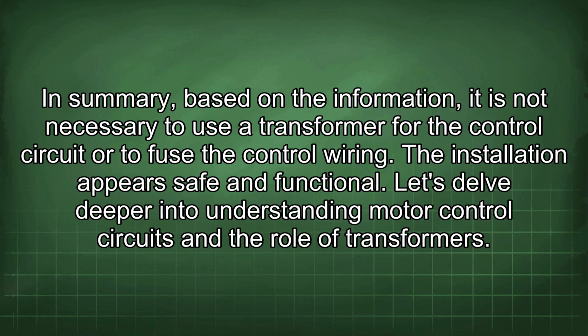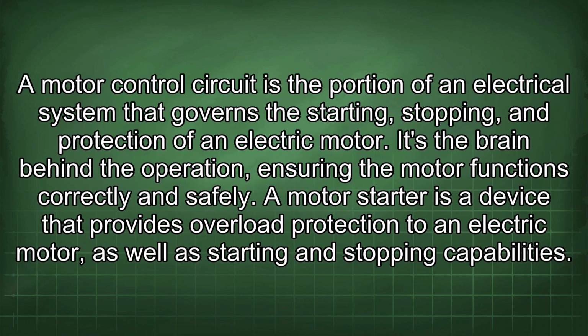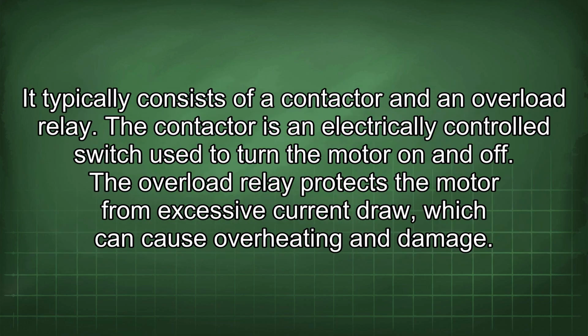Let's delve deeper into understanding motor control circuits and the role of transformers. A motor control circuit is the portion of an electrical system that governs the starting, stopping, and protection of an electric motor. It's the brain behind the operation, ensuring the motor functions correctly and safely. A motor starter is a device that provides overload protection to an electric motor, as well as starting and stopping capabilities. It typically consists of a contactor and an overload relay.